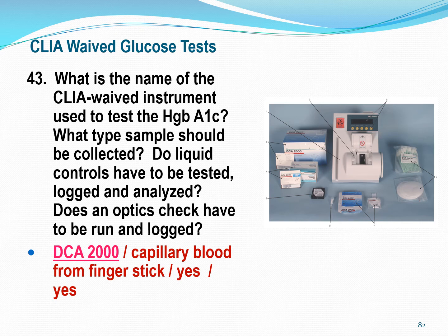If not, you need to troubleshoot it, rerun it, and troubleshoot it until you get the correct answer, or you cannot use that instrument on your patients. And you always want to perform all your maintenance and optic checks on all your instruments and keep up-to-date logs on the fact that it's being done.